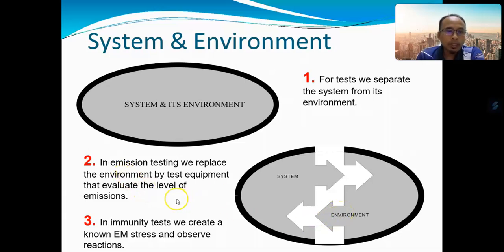And the third is immunity, where we create a known electromagnetic stress and observe the reaction of the medical device. So these are the techniques on how to evaluate the emission level and also the immunity level of the medical device.